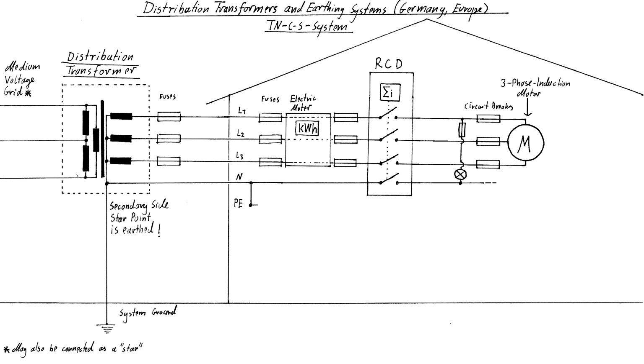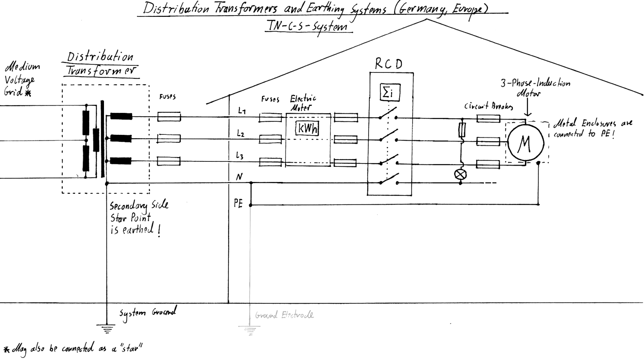Small and medium loads, which require a supply voltage of 230 volts AC, are connected between one phase and neutral, while large loads like this three-phase induction motor are connected to all three phases, while no neutral connection is necessary, as long as the load burdens the three phases symmetrically. All metal enclosures and surfaces, not linked to the phases, are then connected to the protective earth, which needs to be earthed inside or near the house once again. This is done with a ground electrode.